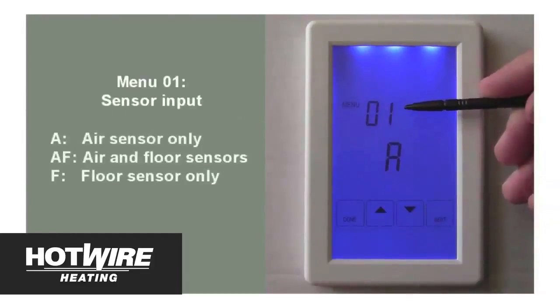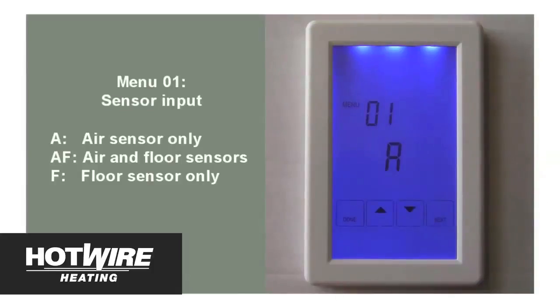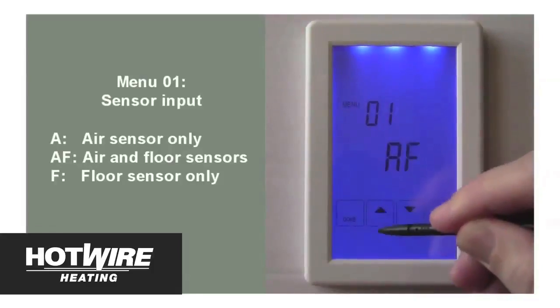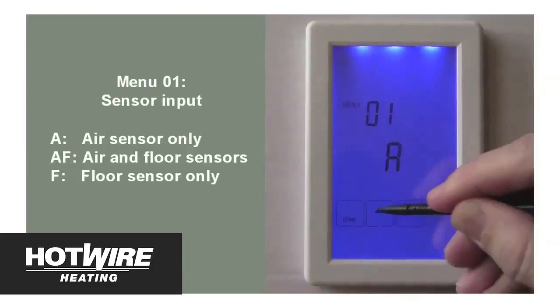Menu 1 and the letter A will show. Menu 1 allows you to choose which sensor the unit will use to determine the floor temperature. You can use the up or down arrows to select between A, where the unit will use its built-in air temperature sensor; AF, where the unit will use its air temperature sensor and the floor temperature sensor together; or F, to just use the floor temperature sensor installed inside your heated floor. In this case, select F and press next to move to the next menu.